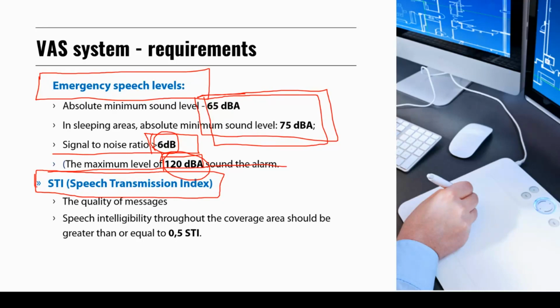The second parameter, which is of the same or even bigger importance than the SPL, is the STI. That stands for the speech transmission index. The speech transmission index describes, on a scale from 0 to 1, the quality of the speech signal. 0 means that we can't understand anything, and 1 is when we can understand 100% of everything transmitted from the speakers. In real life, it's always somewhere between 0 and 1. And we need to make sure that the speech signal coming through the speakers is higher than 0.5 STI.